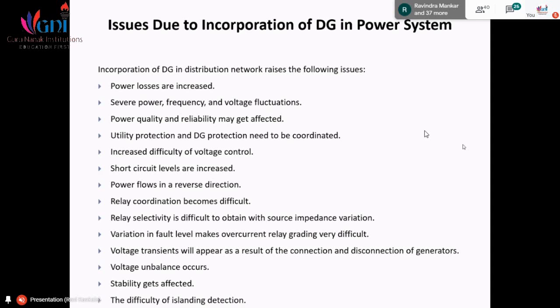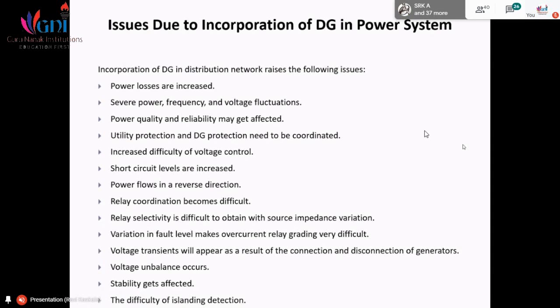The next issue is that utility protection and DG protection need to be coordinated. The utility has its own protection system, and if you are connecting a DG, it should also have protection. Otherwise, if a fault occurs in your power system, the effect may damage your DG. So whatever protection strategies or norms are used for the utility and the grid, the same should apply to the DG system. There should be coordination between the protection schemes, and only then can your system work properly.